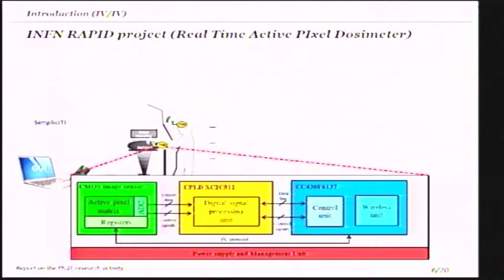The sensor is able to detect x-ray photons. The output of the sensor is received by a digital signal processing unit which implements a data reduction algorithm to extract two observables correlated to the dosimetric quantities. These observables are received by a microcontroller that sends them wirelessly to a remote station using the SimpliciTI protocol.